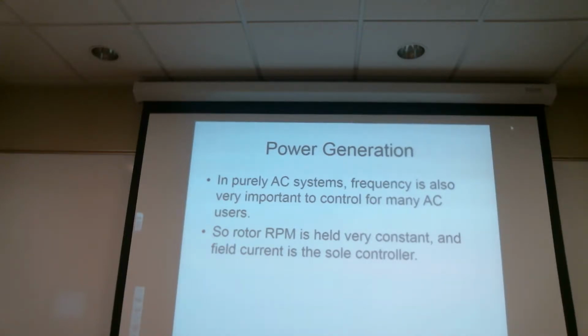I checked it just today, and right now, because of inductive and capacitive reactance imbalance in the building, we're operating at about 0.89 efficiency, or 89% of the power the power company is selling us is being used. The other 11% isn't getting to us. We're paying for it, but it isn't getting to us because of this reactance. So if I change the frequency, everything I designed to control that reactance goes out the window. Instead of being 11% off, I might be 25% off just by changing the frequency 5 or 10 cycles per second.